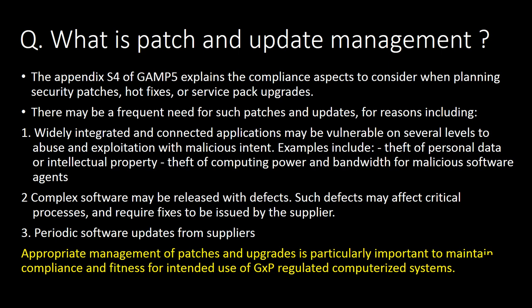What is patch and update management? Appendix S4 of GAMP-5 explains the compliance aspects to consider when planning security patches, hot fixes, or service pack upgrades. There may be a frequent need for such patches and updates for the following reasons: first, widely integrated and connected applications may be vulnerable to abuse and exploitation with malicious intent; second, complex softwares may be released with defects; and third, periodic software updates from suppliers. Appropriate management of patches and upgrades is particularly important to maintain compliance and fitness for intended use of GxP-regulated computerized systems.